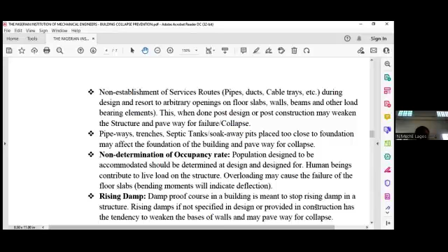If you don't give a schedule of all the holes required for wall penetration, remember some walls are load bearing and some are not. Going through a load-bearing wall may not be allowed by the structure, but if known early enough, a beam can be designed to permit passage. AC ducts can be very big, especially in renovation work, which is more complex than new work because the building is already in place and you're changing the AC system, water system, and so on, puncturing holes and creating cable routes. All this can affect the building's integrity and pave the way for collapse.